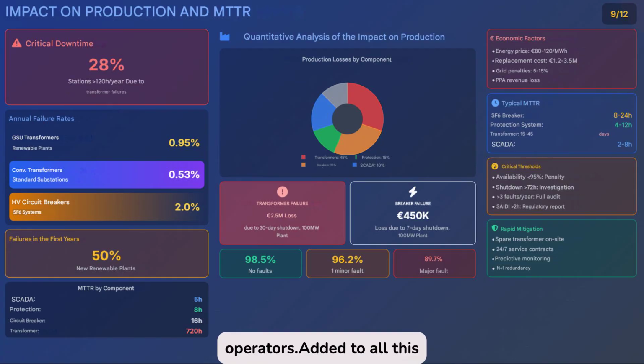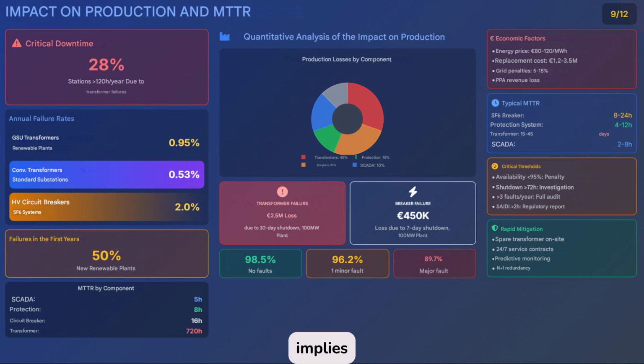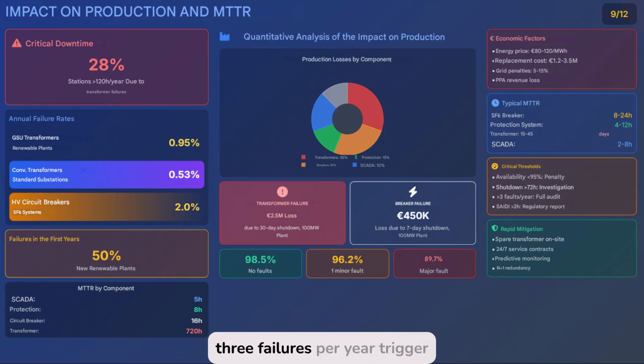Added to all this are critical thresholds that trigger corrective or regulatory measures. Availability below 95% implies automatic penalties. A shutdown of more than 72 hours requires a formal investigation. 3 failures per year trigger full audits, and if the SAIDI exceeds 2 hours, a report must be issued to the regulator. These metrics apply not only to large plants, but also to medium-sized and small facilities connected to regulated grids, demonstrating the systemic scope of downtime management.